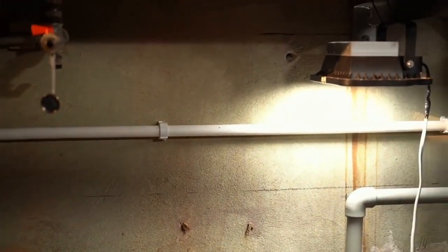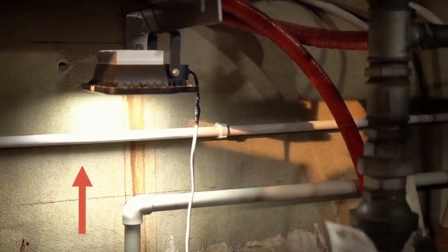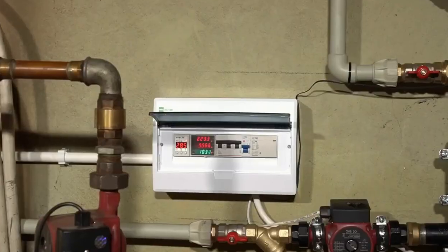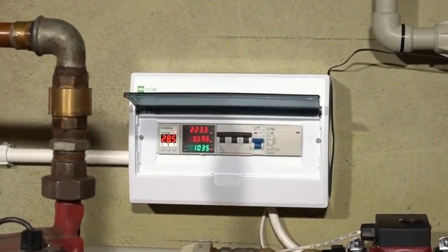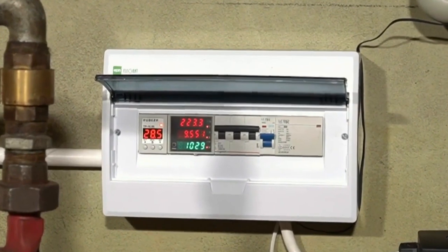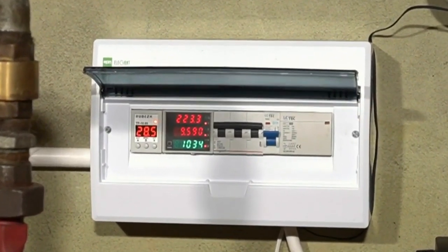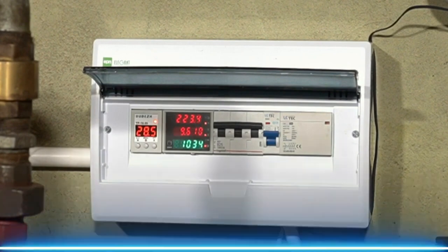We carefully laid the power cable for connecting the electric boiler inside a plastic pipe and securely screwed it to the wall, ensuring a safe and tidy installation. We utilized a 5-core cable with a cross-sectional area of 4 square millimeters. Upon turning on the electric boiler, we measured a phase current of 9.6 amps at a heat carrier temperature of 28 degrees Celsius. This value aligns with the specified values indicated in the boiler's passport, confirming its proper functioning.